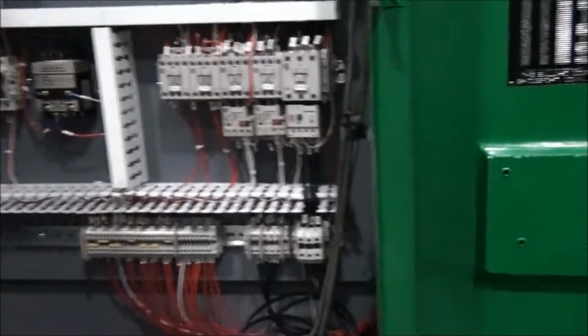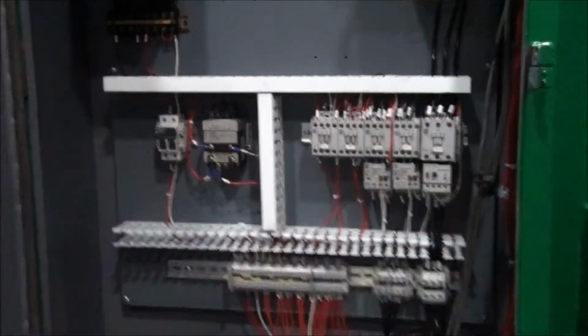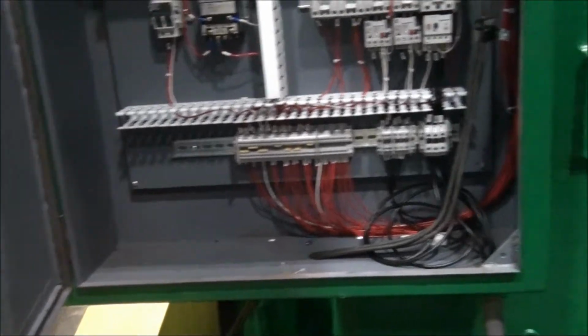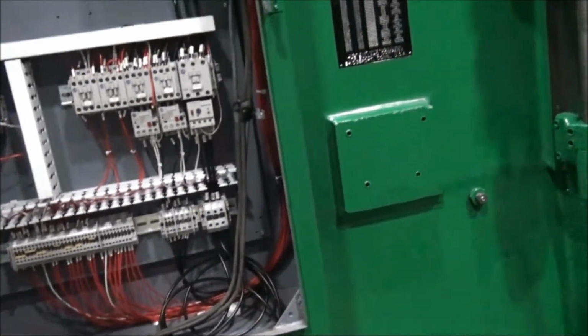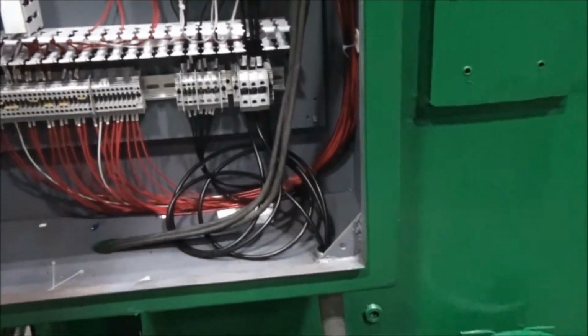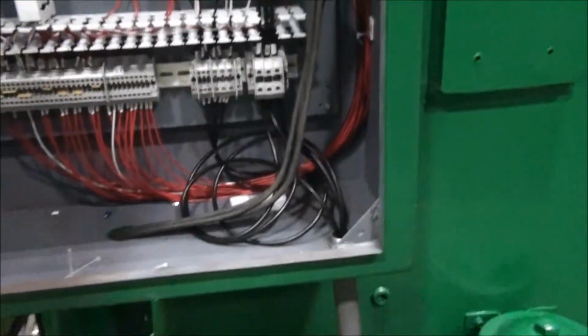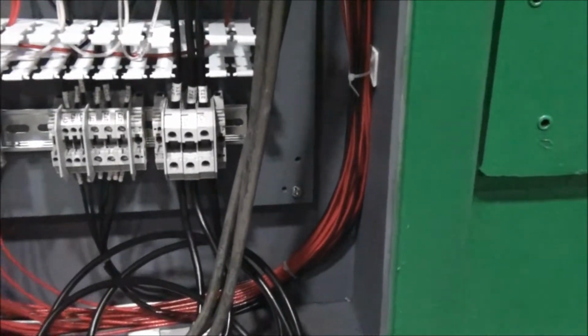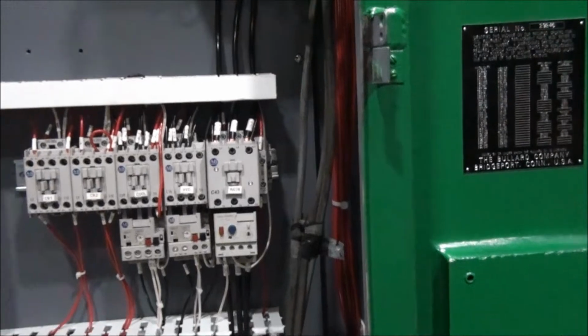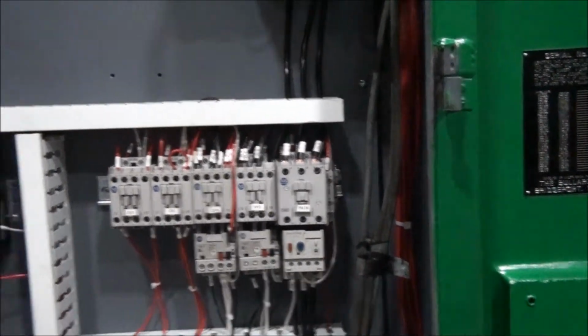Show you the inside of the electrical cabinet. New IEC electrics were installed. 2 kVA transformer for operation of the solenoids. None of the wiring in the electrical panel will need to be reinstalled, with the exception of the main motor. Overloads have been set for the main motor and the hydraulic.